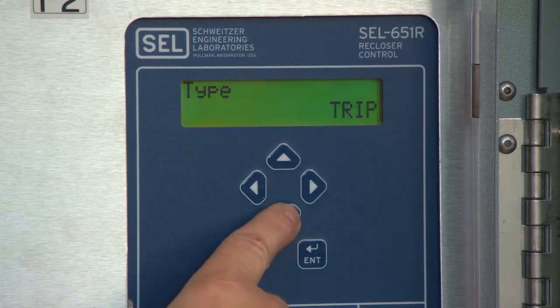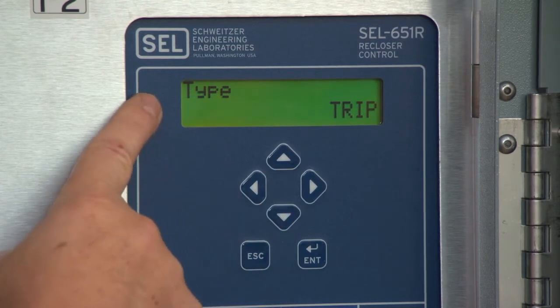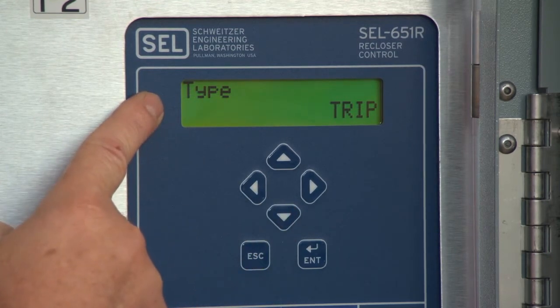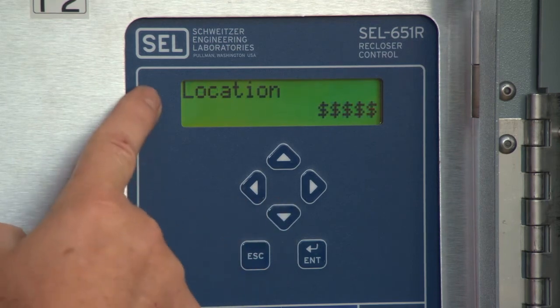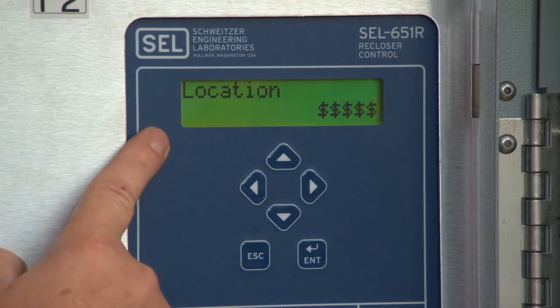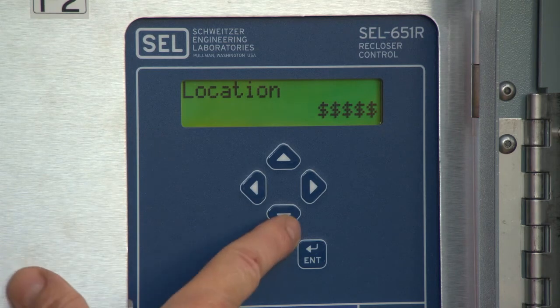Scroll down to see Type, which tells one the type of fault that occurred. In this case, it was a manual trip. Press down again to see Location. If programmed, this would display the distance to fault. This feature is not programmed in 90% of controls and will return a result with number of $signs.